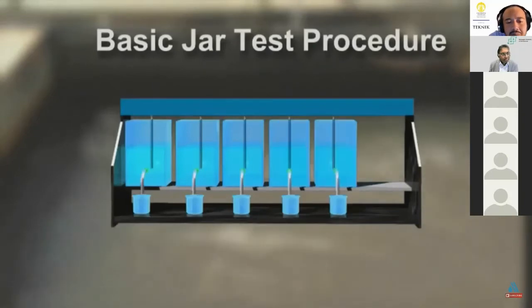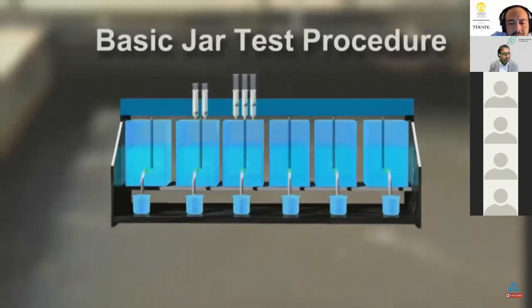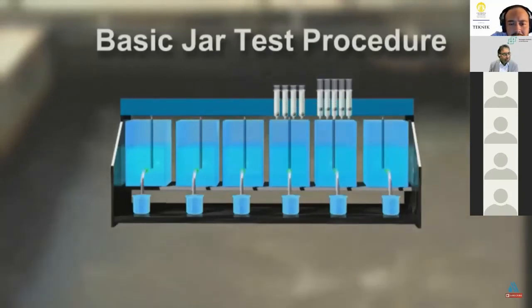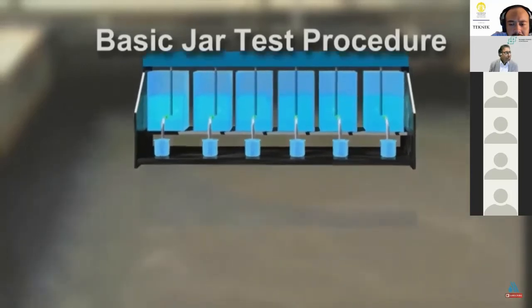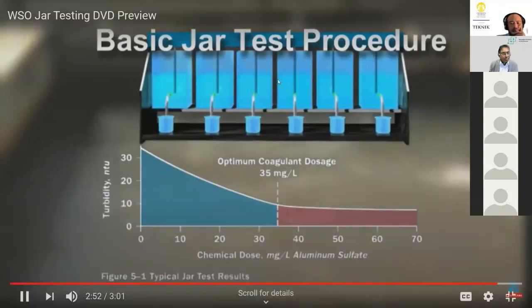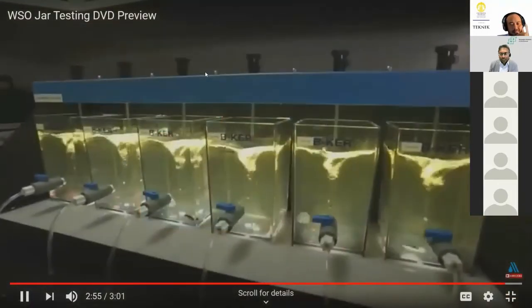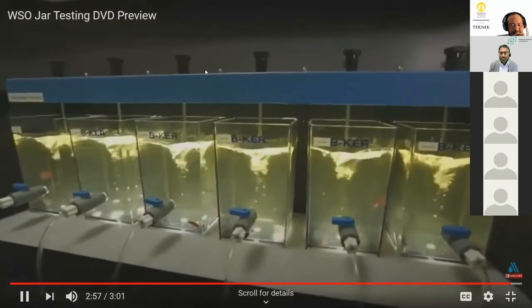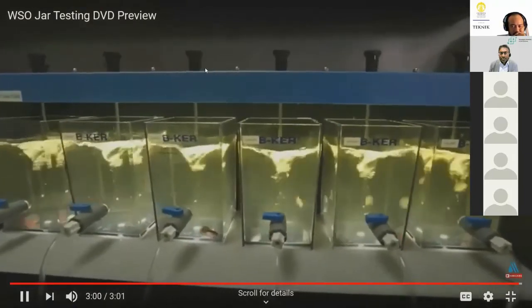The basic jar test procedure involves collecting a raw water sample and adding progressively larger doses of coagulant chemical to several jars. Results identify optimal conditions for turbidity removal. Multiple jars are typically used to examine different conditions and simulate multiple treatment characteristics.